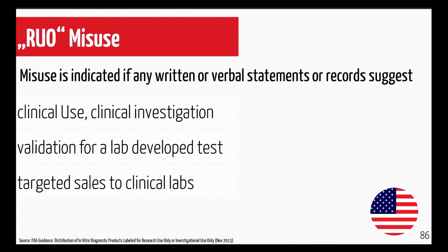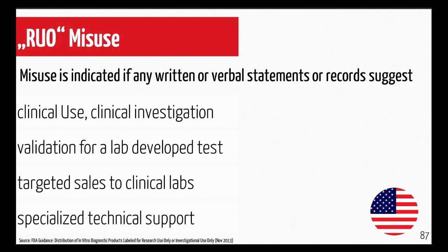Your customers should not only be clinical laboratories, and in the case that they are, I would add a statement or even a contract that these customers do not use the product for diagnostic purposes. And if anyone would provide specialized technical support, for example, to validate the test or any validation services, that would be a critical scenario.